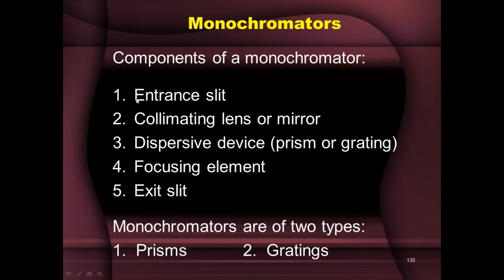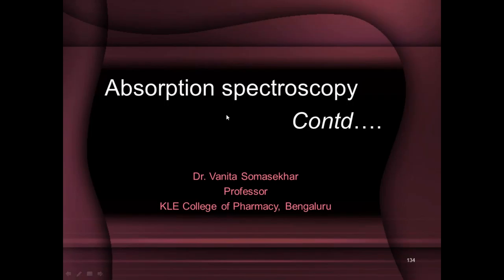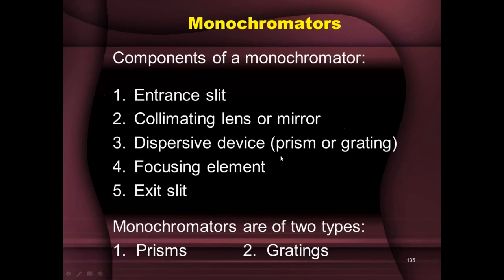So that was what we saw last time — comparing the two filters. Today we'll start with monochromators. What are monochromators, and what are the basic components? All monochromators will have an entrance slit, a collimating lens or mirror to make the radiation parallel, and a dispersive device which spreads out or disperses the different wavelengths. This could be a prism or grating.